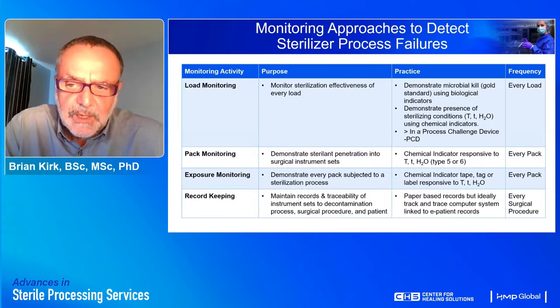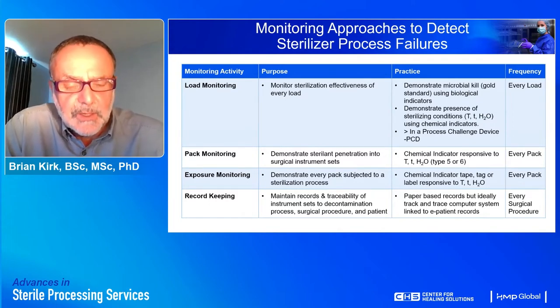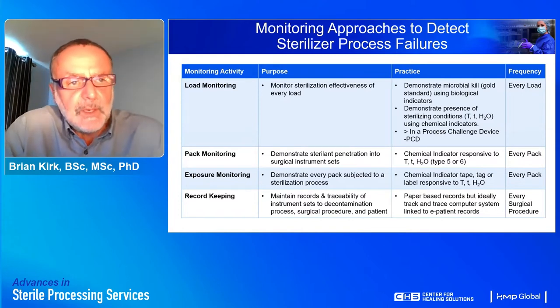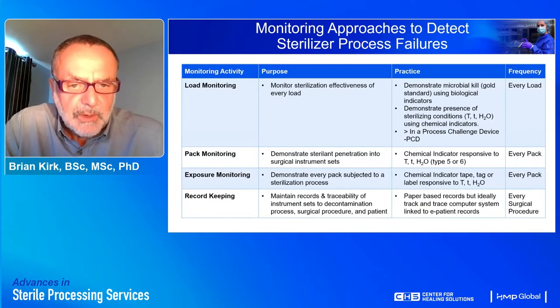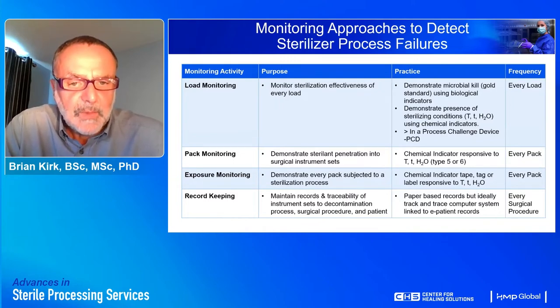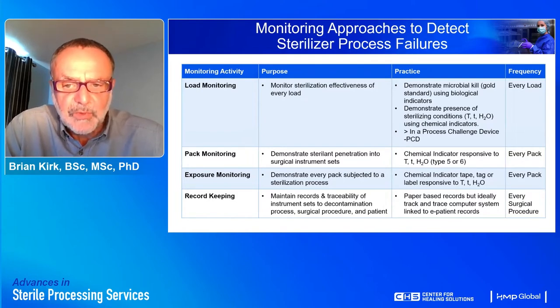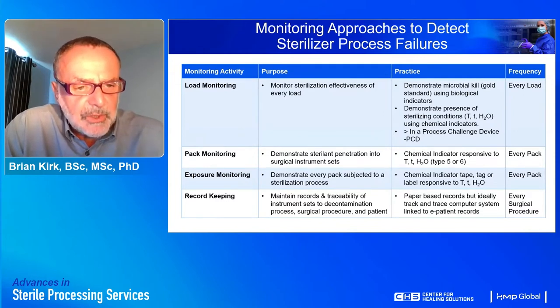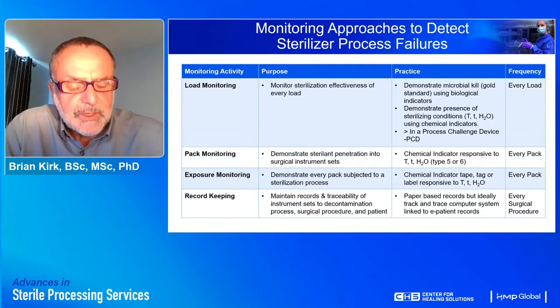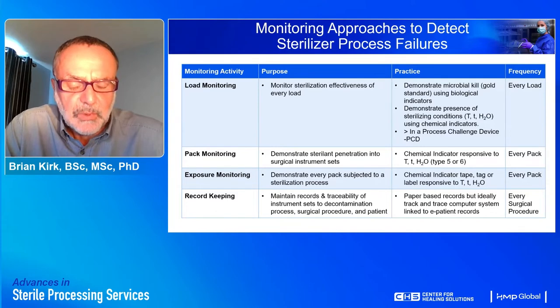Every pack should have a process indicator placed on its external surface so that people can clearly see that a pack has either been processed or not. The scientific literature still reports incidents where surgeons have used non-sterilized instruments, essentially because clear evidence of processing was not provided by a process indicator on the outside of the pack. As with any quality-based system, we should keep good records of the processes and the loads processed during normal SPD operations.